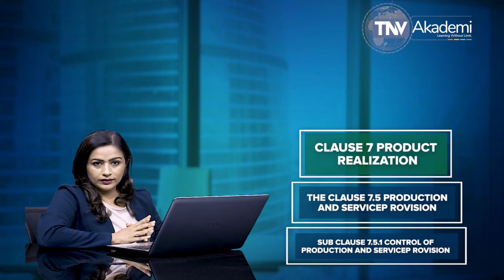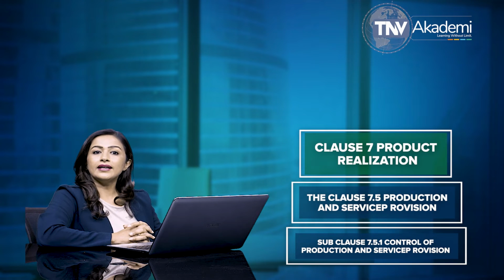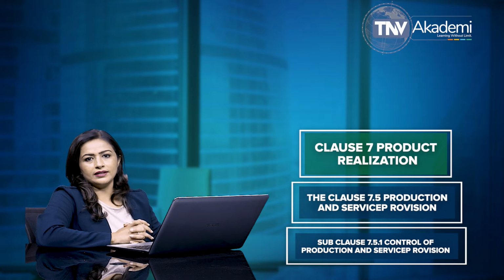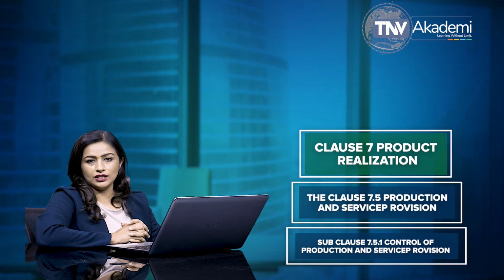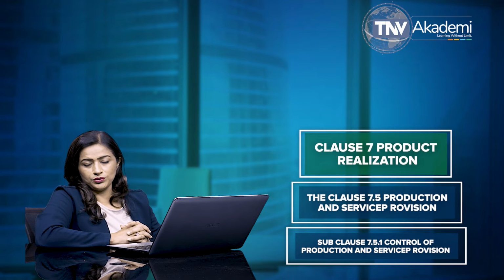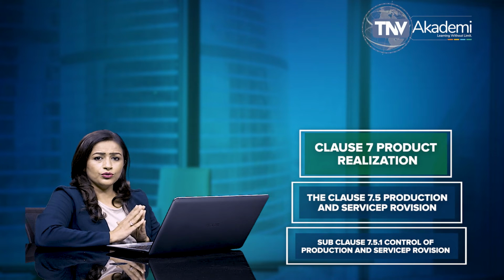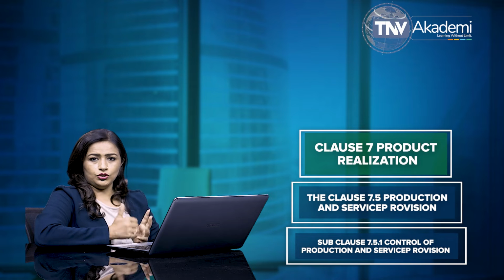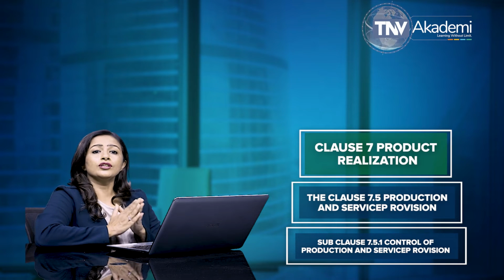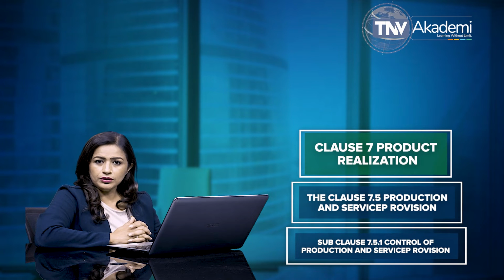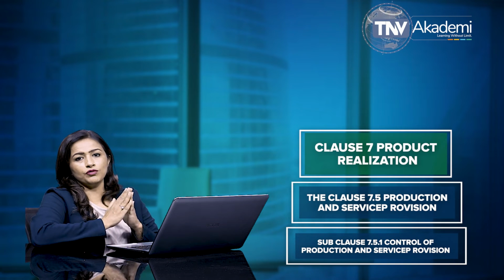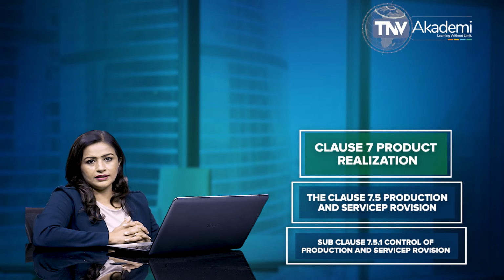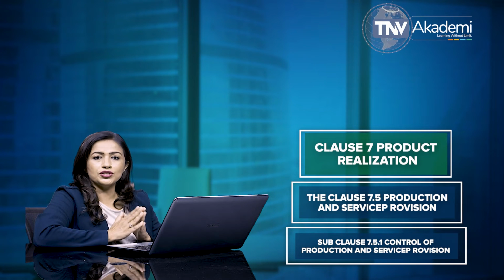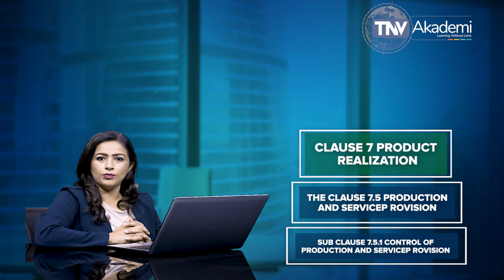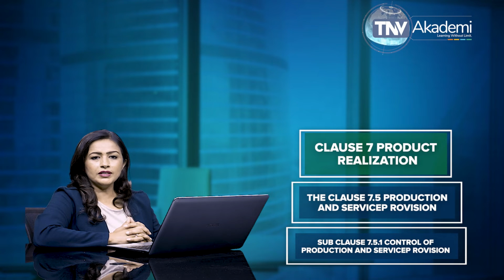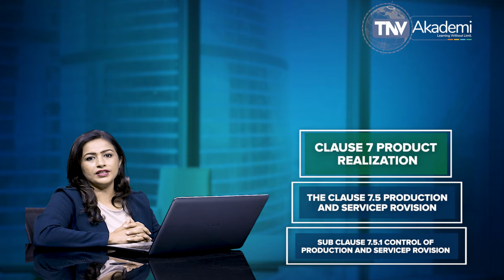Subclause 7.5.1, control of production and service provision, states that the production and service provision is required to be planned, carried out, monitored, and controlled by the organization to ensure that the product conforms to the specifications. According to this subclause, the production controls must include, but are not limited to, documentation of procedures and methods for the control of production, qualification of the infrastructure, implementation of monitoring and measurement of process parameters and product characteristics, availability and use of monitoring and measuring equipment, implementation of defined operations for labeling and packaging, and implementation of product release, delivery and post-delivery activities.